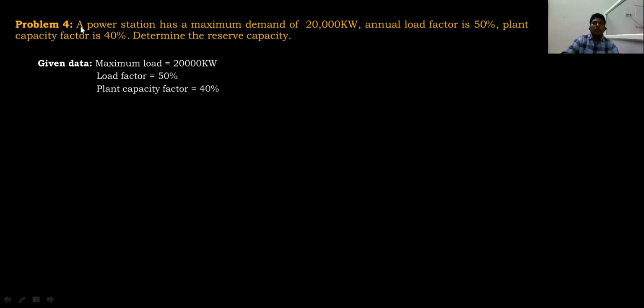The next problem: a power station has a maximum demand of 20,000 kilowatts. Annual load factor is 50%. Plant capacity factor is 40%. Determine the reserve capacity. The formula for reserve capacity is equal to plant capacity minus maximum demand. Maximum demand is already given in the data, so we need to find the plant capacity. Here the plant capacity factor is given as 40%.